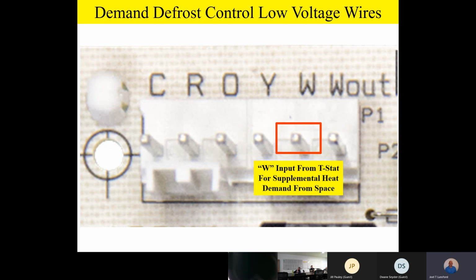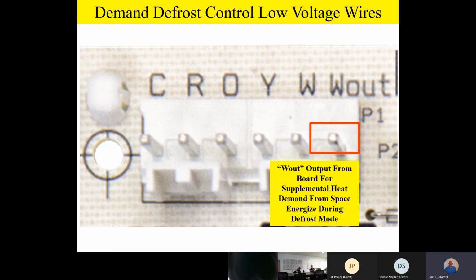W is an input from the thermostat for supplemental heat, and it's the demand from the space. So basically, once the thermostat sees a call for supplemental or auxiliary heat, it'll send a signal out to the W terminal, and then that W terminal is just a relay on board that defrost control board that's going to loop that W signal through the defrost control board back out to what we call W out.